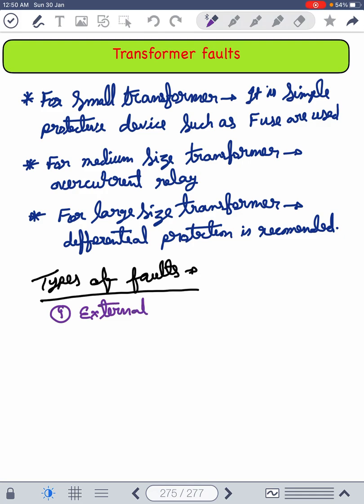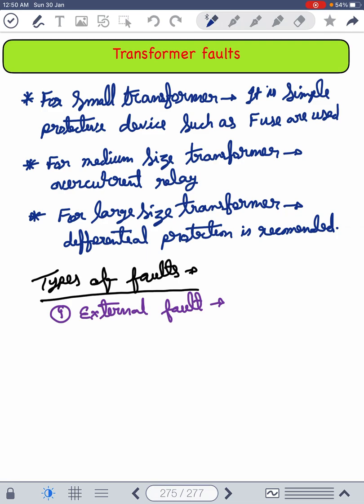In the case of external faults, the transformer must be disconnected if other protective devices fail to operate for such type of faults or fail to operate within the predetermined time. For external faults, a time-graded overcurrent relay is used.